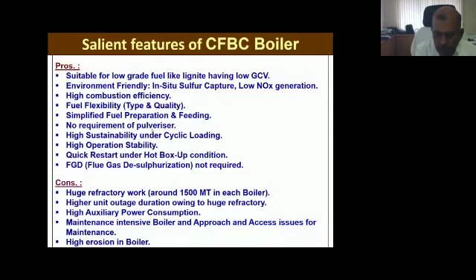In this boiler, we are using bed material, which is nothing but our bed ash, which has erosion properties. So once it circulates in the boiler or slides on the wall of the combustor, it causes heavy erosion, and that is a major reason for outage of boilers. For that, we have taken different measures. Refractory has been provided in certain areas for the transient zone. Then we are using metal spray coating in the high erosion prone areas.